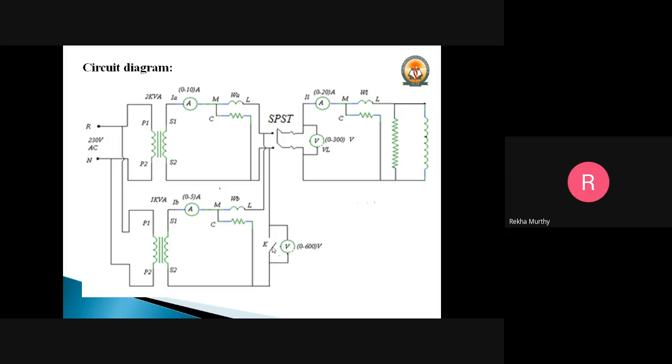Loading will be continued in steps of 2 amperes by varying both the resistive and reactive loads. Care should be taken in such a way that the ammeter which is connected to the secondary should not exceed the rated current of the corresponding transformer.